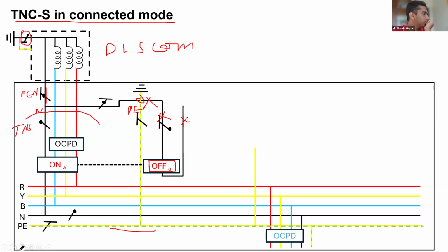What I mean is, in simplified terms, this will be a PEN conductor. On top, this will be a PEN conductor, and from this PEN conductor there will be a system referencing done here, and from here it will be neutral, and from here it will be a PE. So this will be on and this will be off. So this is how it is. It is in TNCS. This is in connected mode. In connected mode, this is a TNCS system.